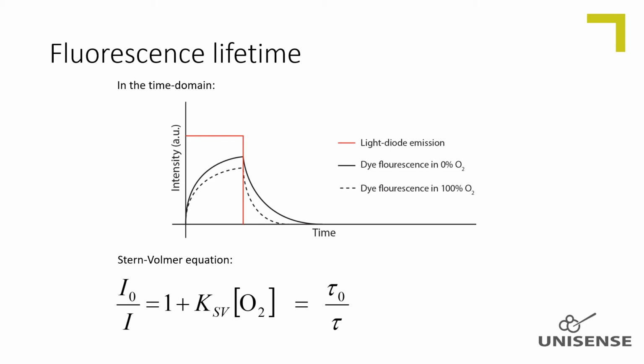This is illustrated here. The intensity increases during the light diode emission period, and when the emission stops, the intensity decreases, but it decreases faster with oxygen in the polystyrene/dye matrix than without oxygen. This so-called tau response is only to a minor extent affected by the amount of dye, and therefore a much better parameter to utilize than the intensity.